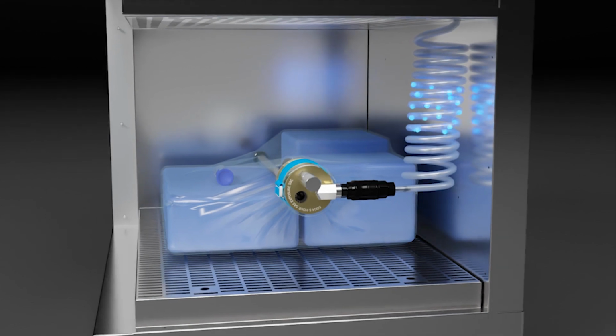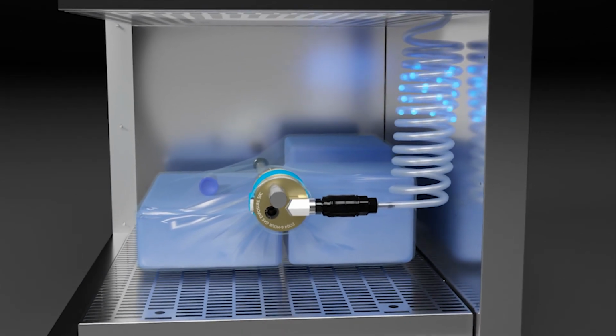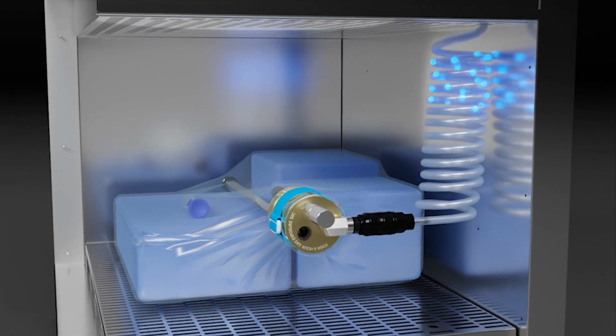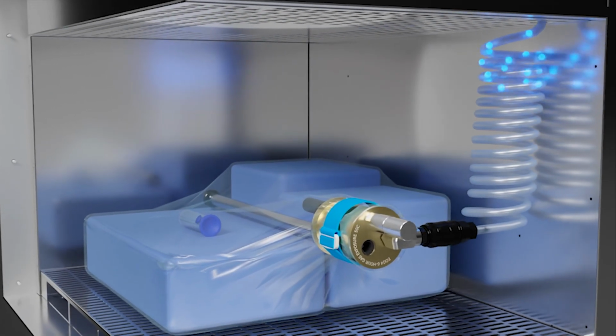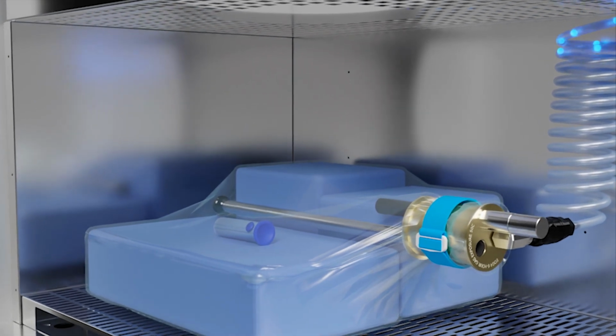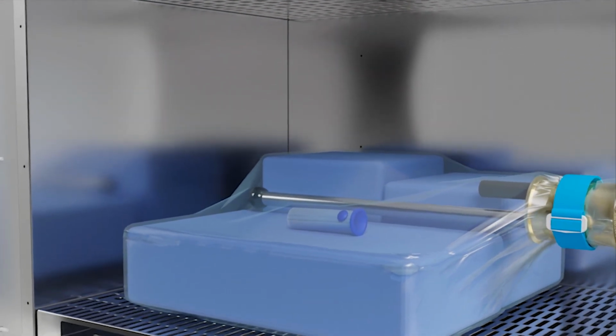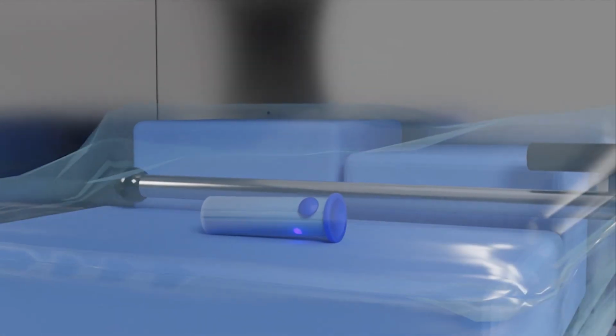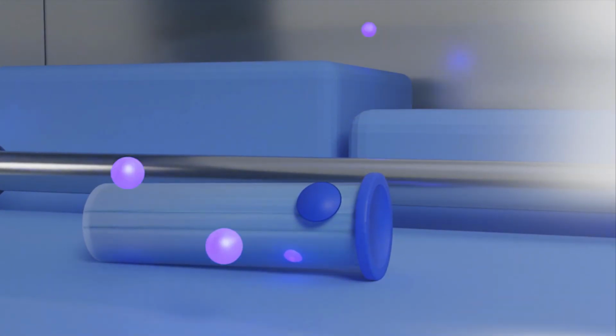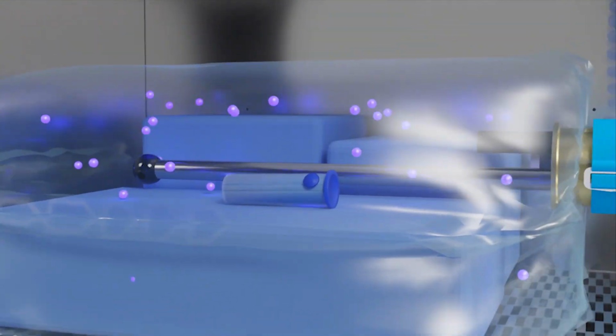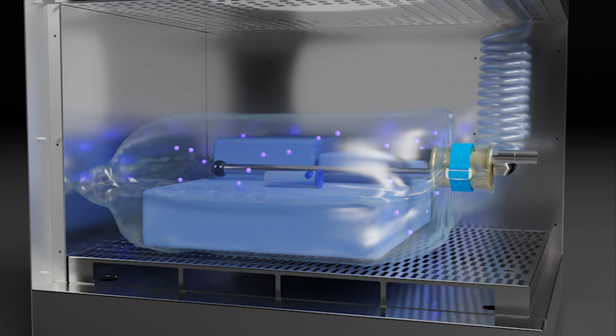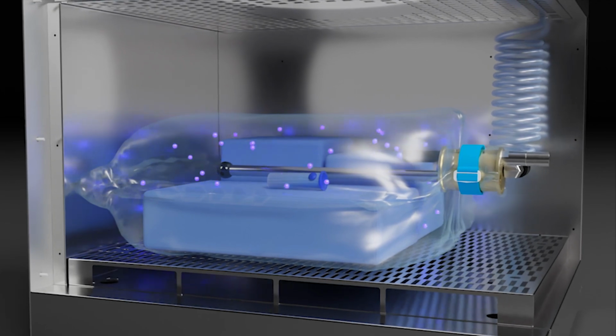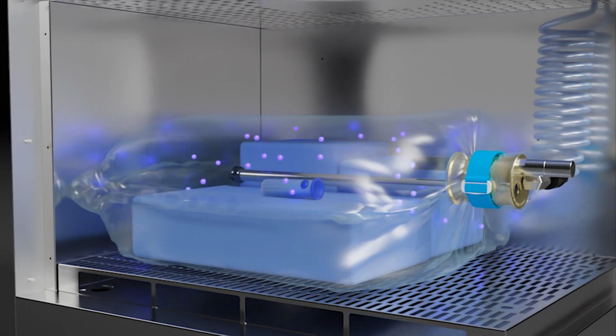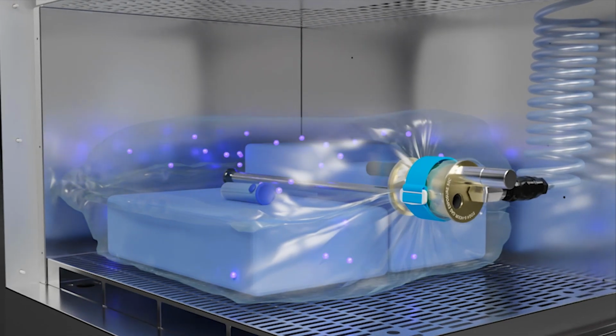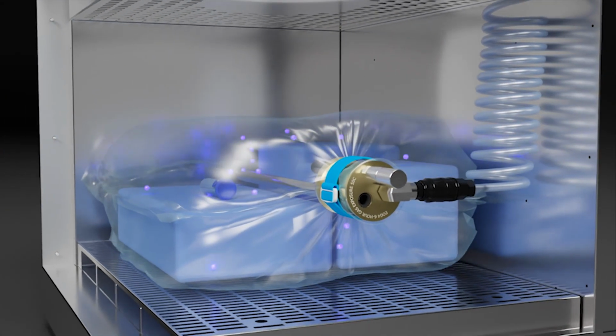Air molecules, represented by the blue dots, are exhausted from the sterilization bag through the purge probe and purge tube. With excess air removed, the ethylene oxide, EO or ETO, concentration in the sterilization bag is maximized during sterilization, thereby minimizing the amount of EO needed for effective sterilization. Once the initial purge is complete, the gas cartridge is manually activated by pressing the button on the cartridge through the wall of the sterilization bag. Ethylene oxide, represented by the purple dots, spreads throughout the sterilization bag and permeates the items being processed. The gas-impermeable flexible chamber maintains a high gas concentration during the sterilization cycle.